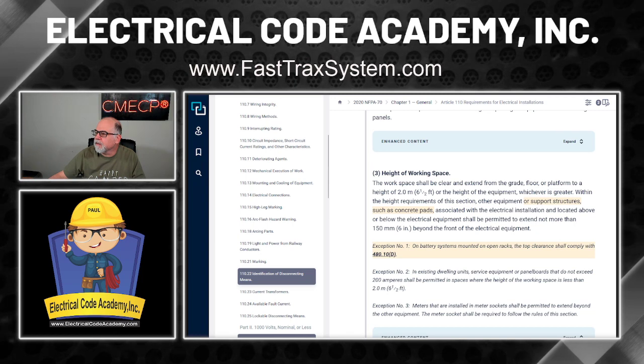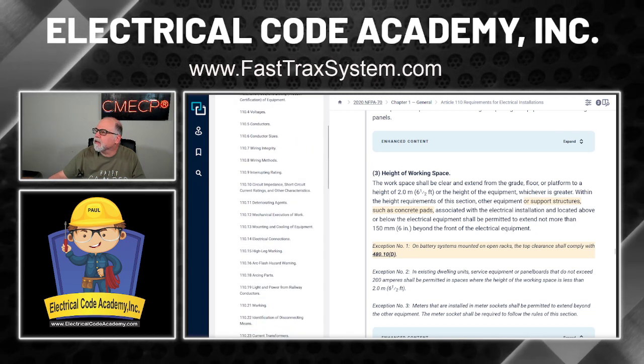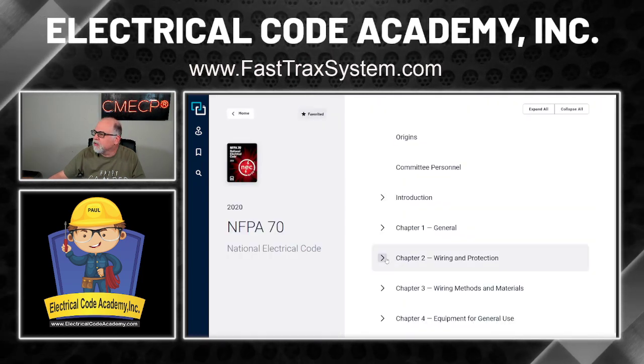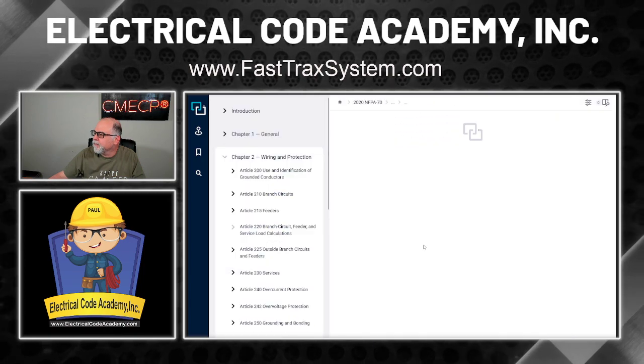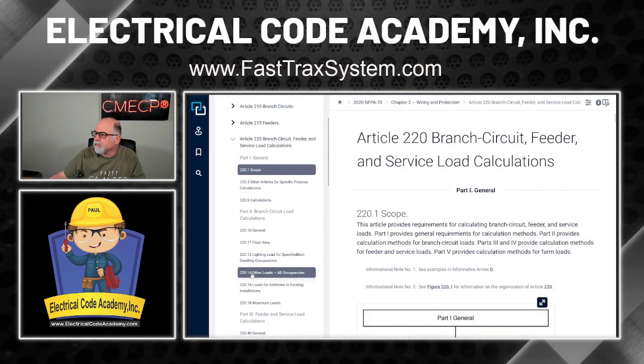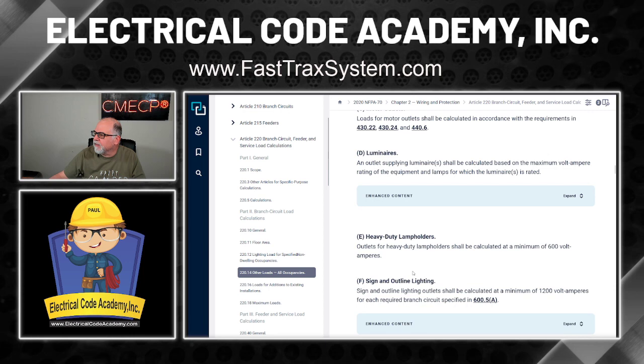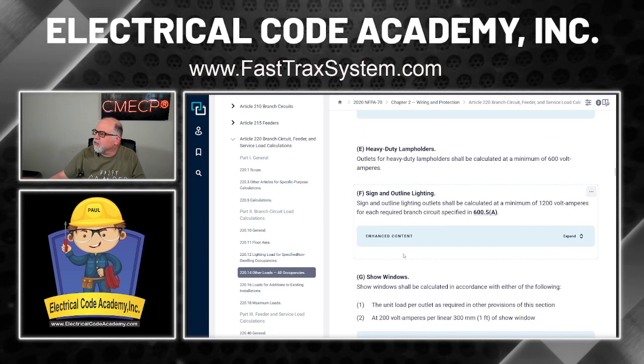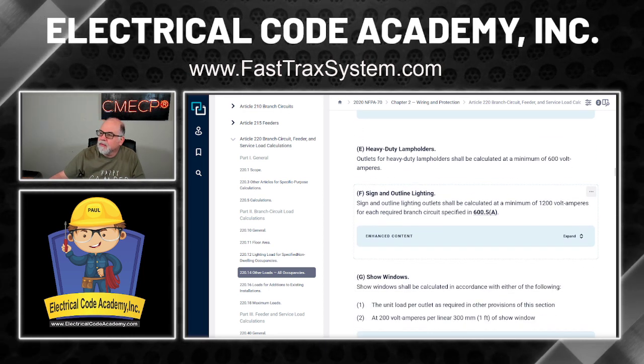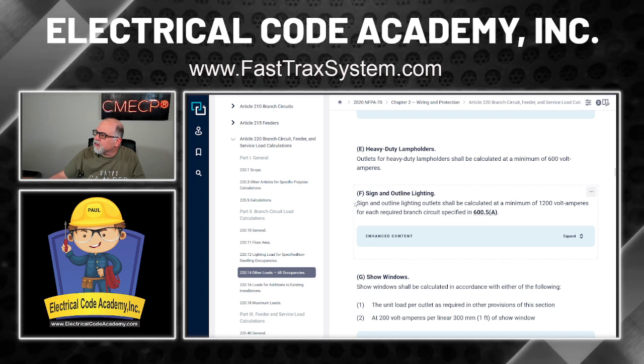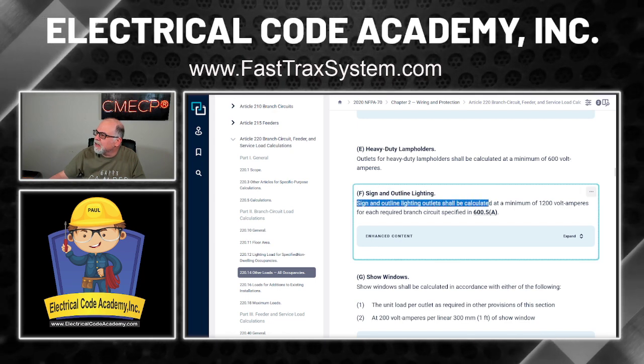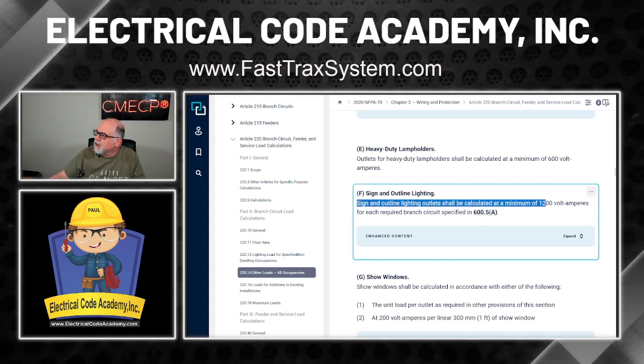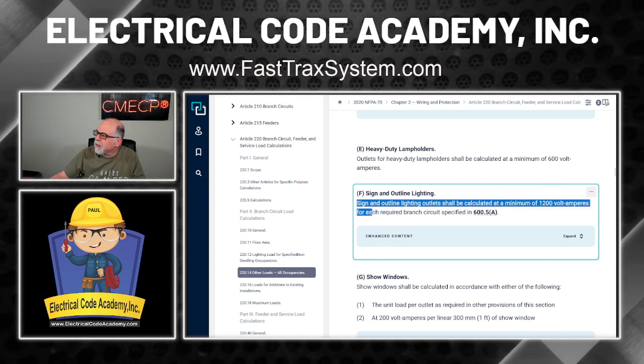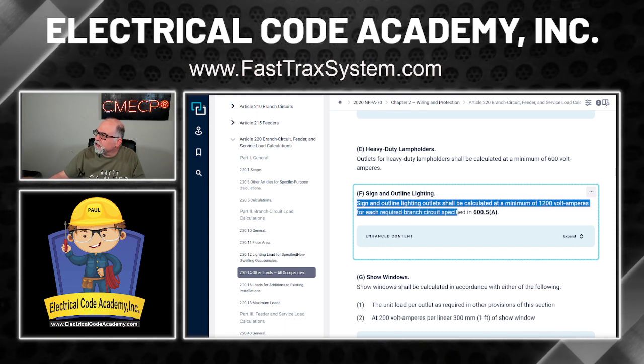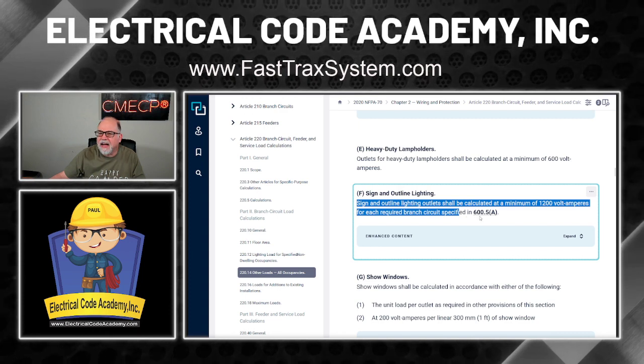And let's see here. Go back to the code here. Let's go to 220.14. Right here. And we got to go to F. All right. Here's F right here. Okay. Now it says, sign and outline lighting circuits shall be calculated at a minimum of 1200 volt amperes for each branch circuit specified in 600.5(A).